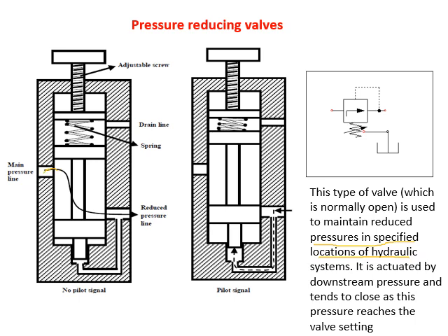You can see that the fluid is flowing freely through the spool, but when the downstream pressure rises above a certain limit, it puts a pressure from the downstream side of the spool, and it will try to close the downstream port, and it will close that at one particular time. It will completely close that port so that the pressure at the downstream side will reduce.